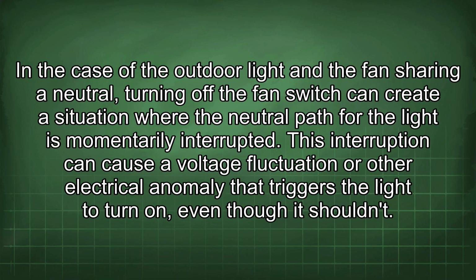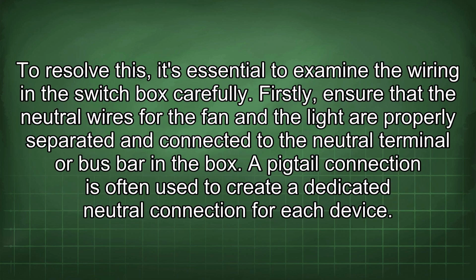In the case of the outdoor light and the fan sharing a neutral, turning off the fan switch can create a situation where the neutral path for the light is momentarily interrupted. This interruption can cause a voltage fluctuation or other electrical anomaly that triggers the light to turn on, even though it shouldn't. To resolve this, it's essential to examine the wiring in the switch box carefully.